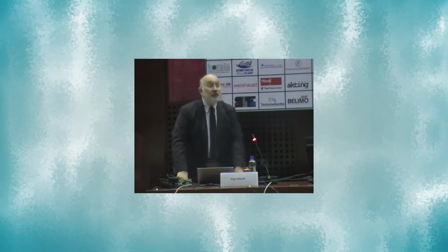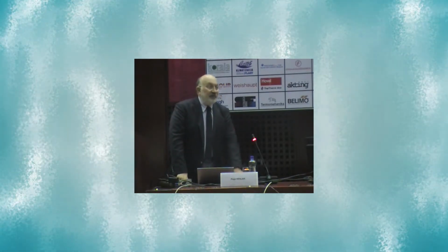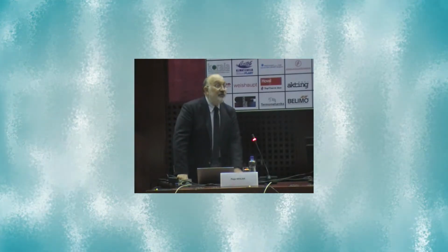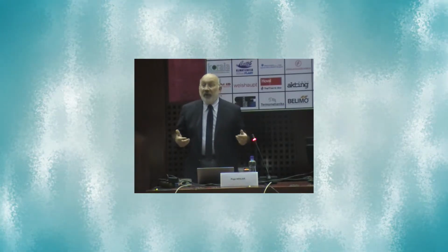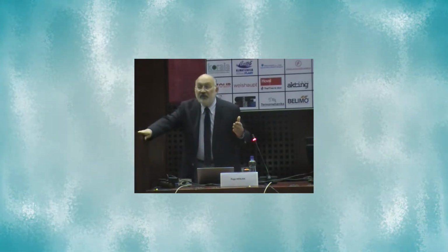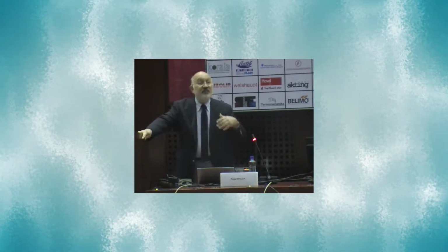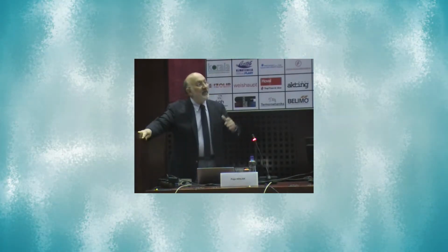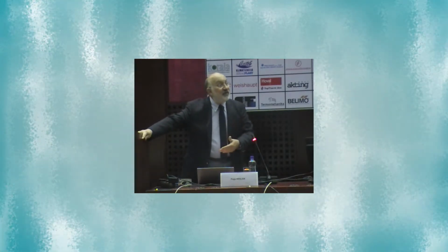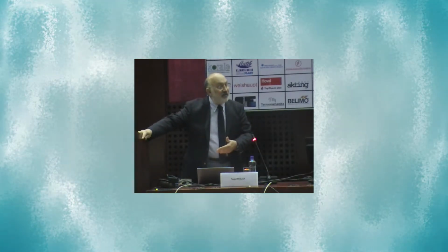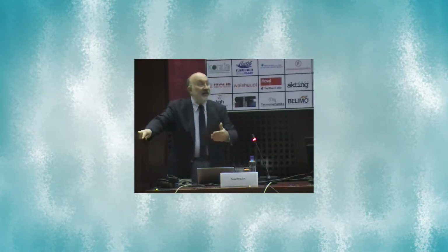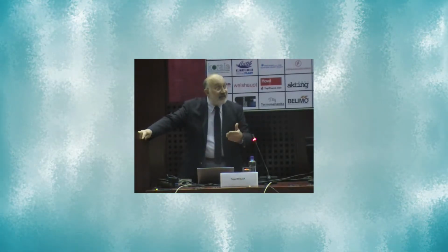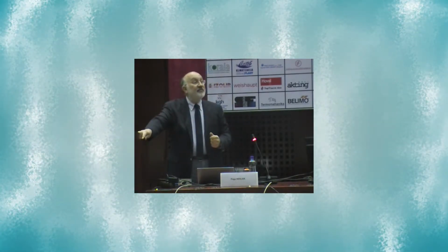We evaporate with water. Why do we evaporate with water? We want to have uniformity, even better than maybe needed. That's number one. And number two, this facility was really originally made for condensation. So the same facility can be used for evaporation and condensation. And this is the facility where we have measured especially condensation of CO2 at minus 30 degrees C, minus 15, minus 10. This is very important for cascades.